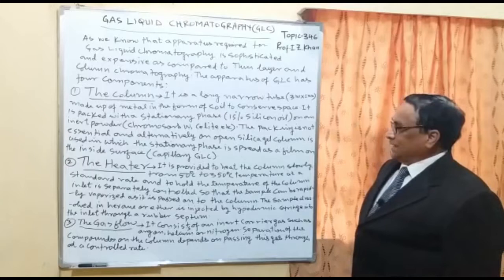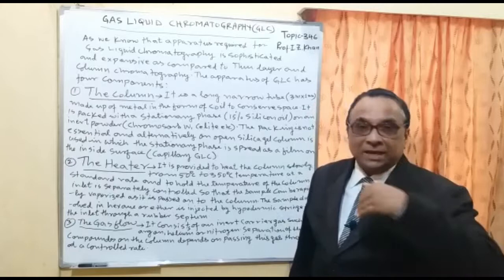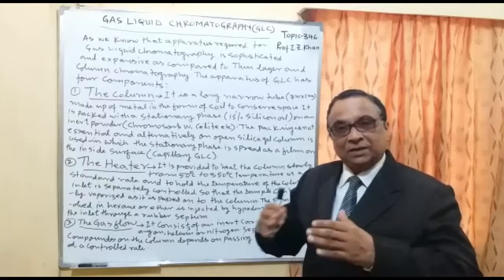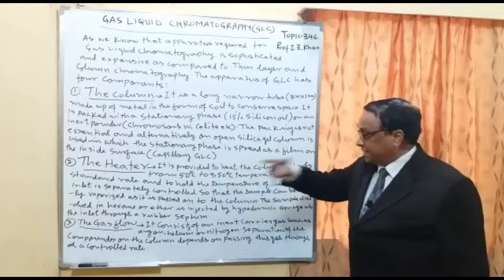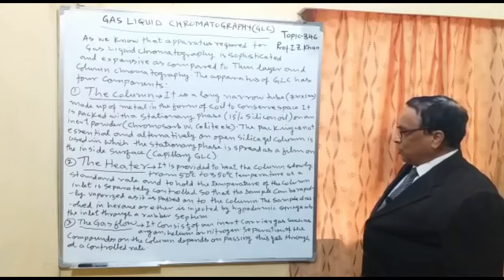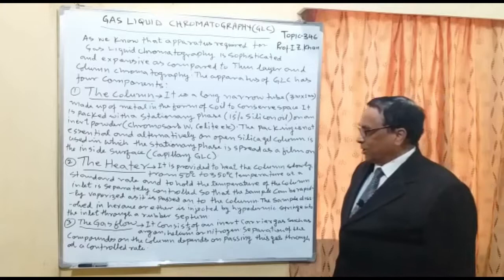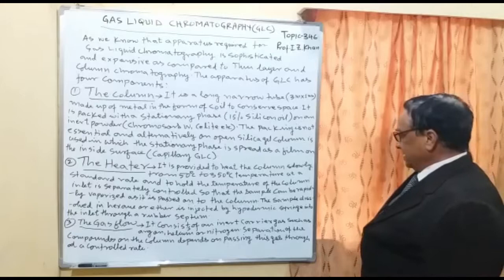Component number two is the heater. The heater provides very high temperature so that even if the component is in liquid form, it changes into vapor form. It heats the column slowly from 50 degrees centigrade up to 350 degrees centigrade at a standard rate. The column inlet temperature is separately controlled so that the sample can be rapidly vaporized. The sample, dissolved in hexane or ether, is injected by a hypodermic syringe into the inlet through a rubber septum.